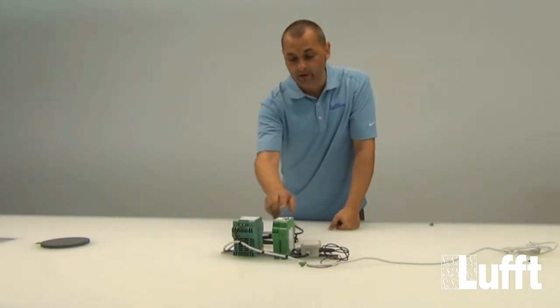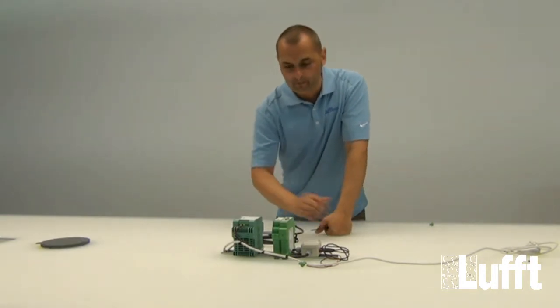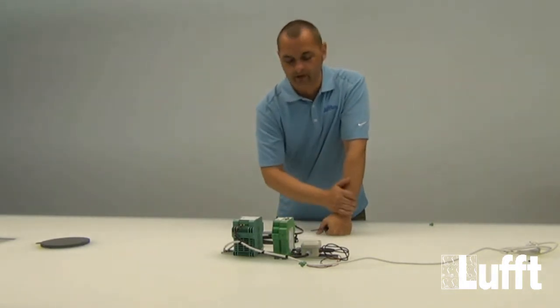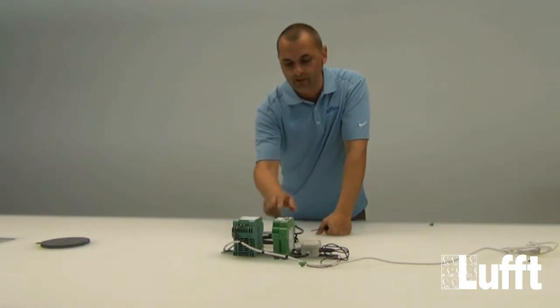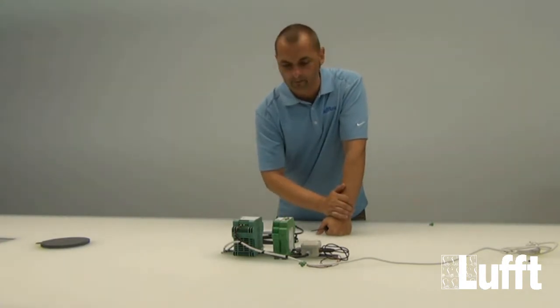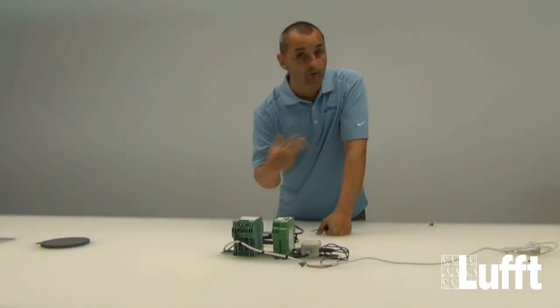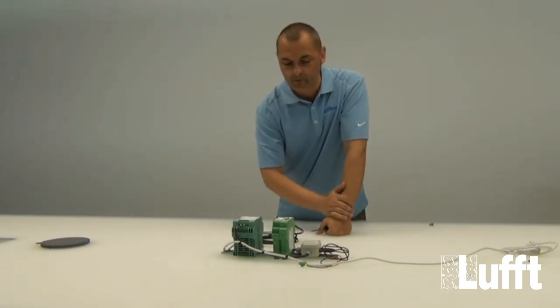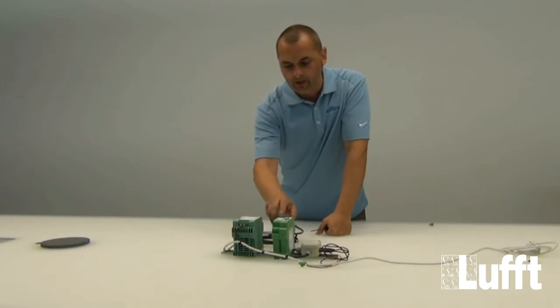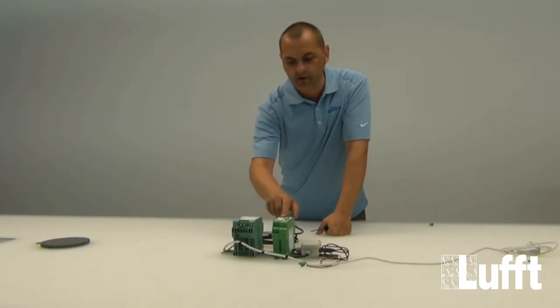I want to tell you another important thing here. If you have more than one Anacon per system, you need to address this Anacon. So if you have two or three, you need to give them the address 1, 2, and 3. Also, this will be done with the UMB Config tool anyway. And you can mark this ID here on the sticker.